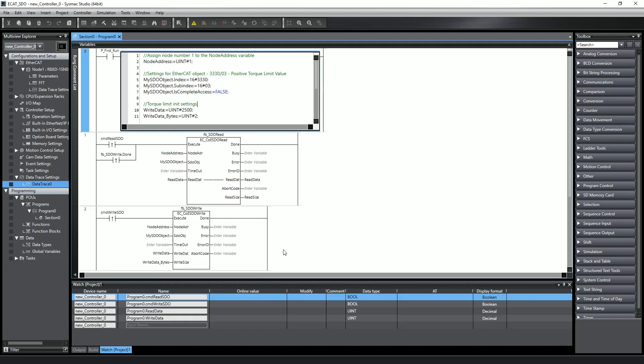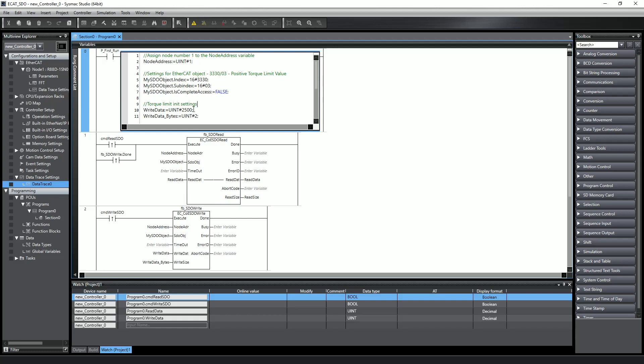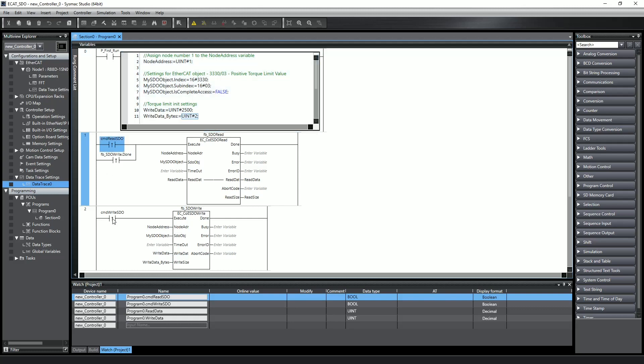The object table shows that the data type for the positive limit is unsigned 16-bit, so I set my read data and write data variables as unsigned integers. I put initial values into the write data and write data bytes in the structured text block to have a starting point. Lastly, I created contacts to execute the function blocks, and I automatically execute the read function block after executing the write function block as a verification.